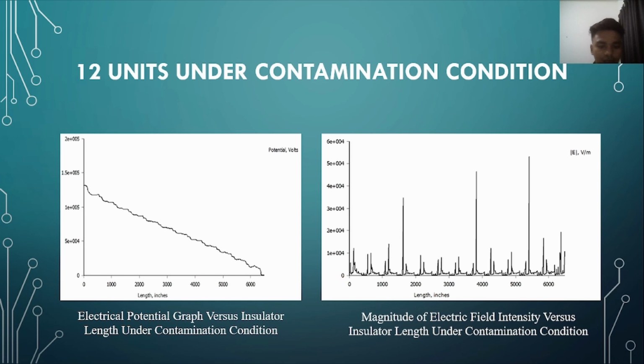Ceramic insulators are often exposed to high pollution levels, such as marine and industrial pollution, which degrade their performance. Insulator pollution causes an undesirable response in the form of an increase in leakage current owing to the high pollution rate. Stress is applied to the insulator surface and the contaminated layer.